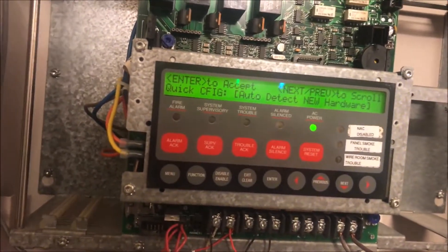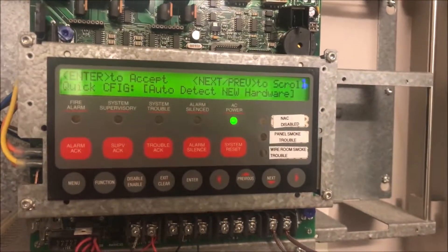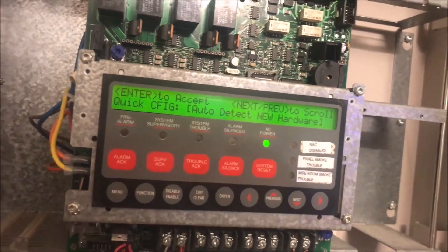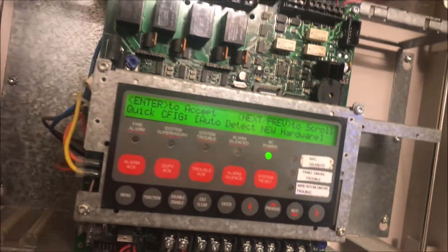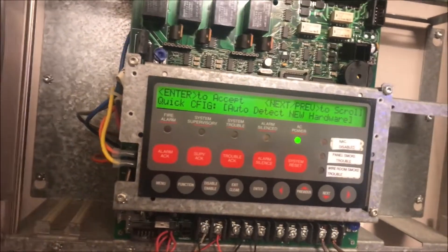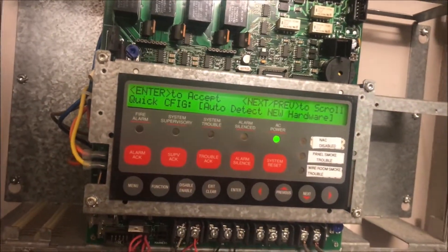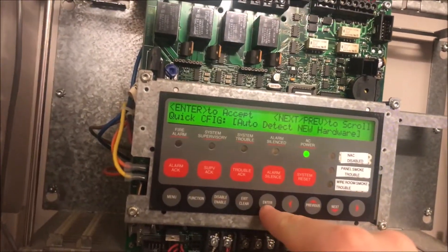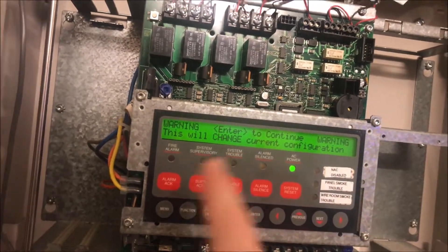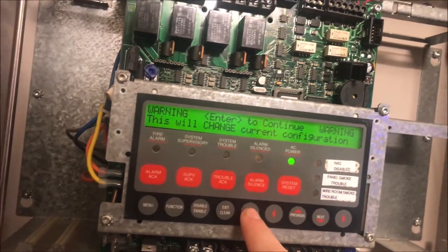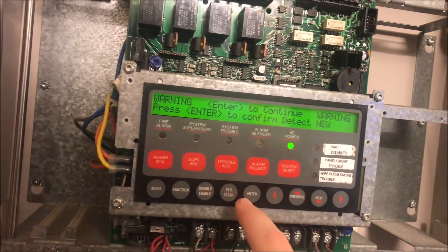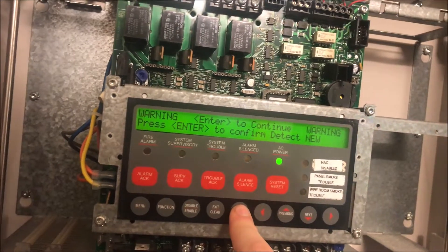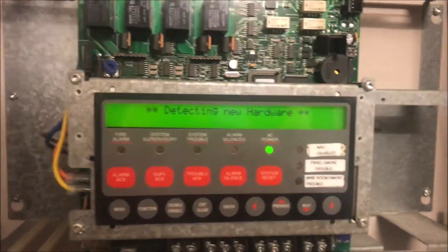This is under level four menu, quick configuration, auto detect new hardware. The other way to do this is to go level four, programming, configure points, add new IDnet point. This is the way I do it because it gets all my settings in and everything, and all I have to do is hit one button. We're going to hit enter, it's going to give us a warning, and we're going to confirm detect new hardware.